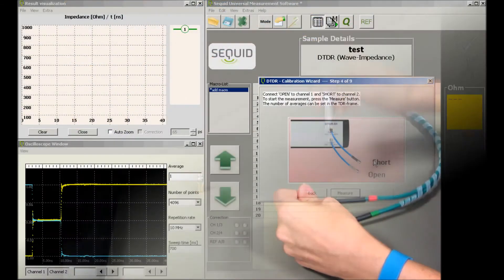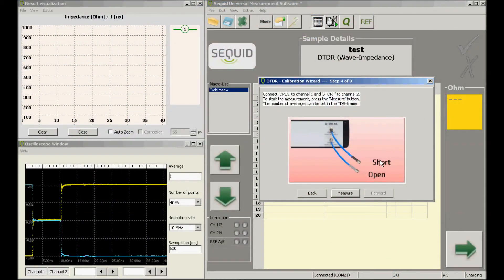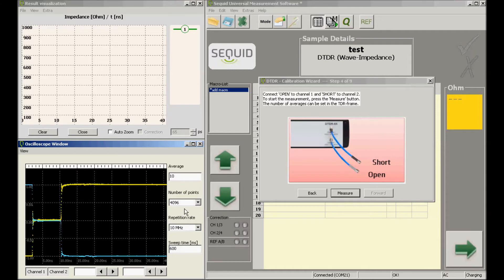We now change the number of averages to 10, which is a proper value for calibration purposes. The other settings are left unchanged. We use 4096 data points and the repetition rate of the step signal is 10 MHz. These settings prove to be suitable for most impedance measurement applications.